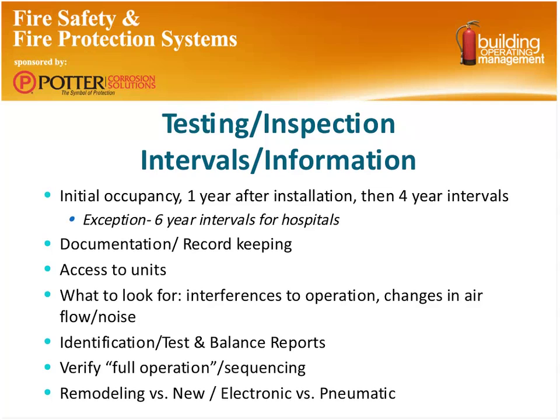It's really not a function test, but it's a visual inspection just to make sure that the damper is in place, and take a quick look at it to see really what it looks like. And we'll see that here in a minute with some of the pictures that I have. They're a little more self-explanatory of why this is an important function. There should be documentation and record keeping, and that's by code supposed to be available for your local authority, whichever one that might be.